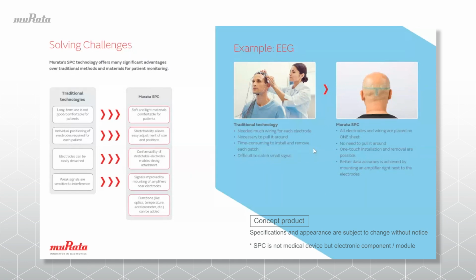Stretchable printed circuits can enable a design which fits the challenging curvature of the skull, for example, enabling long wear time while keeping the risk of skin damage low, especially when the patient is lying down, and the soft and conformable materials can minimize pressure points. In addition, this concept can secure high accuracy due to the good adherence of the electrodes, in combination with the mounting of amplification and, for example, inertial sensing for high robustness against movement artifacts and noise. And this can all be realized on a single patch.